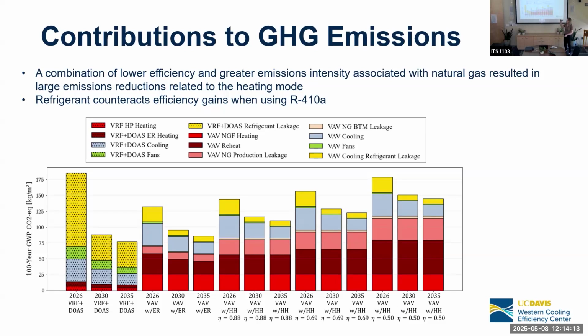However, we really need to look at refrigerant too. So refrigerant is in the yellow bar at the top. And you can see for 2026, we're using R410A, and VRF and DOAS is not really advantageous compared to any of these on an emissions basis because of all the refrigerant leakage. Once you switch to R32, you have some benefit, but there's opportunity for improvement if we can reduce that leakage rate.